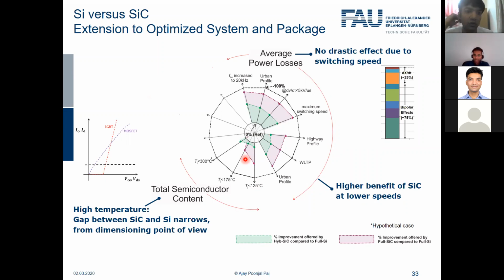Higher junction temperature, TJ. So the gap between silicon carbide and silicon becomes narrow at higher temperatures. How do I explain that? Once again, with respect to this picture: when you dimension a module for a higher junction temperature for the same chip area, you can allow a higher RMS or higher current in the device. So the current the module can take at 175 degrees Celsius or at 300 degrees Celsius will be much higher than what it can do at 125 degrees Celsius.